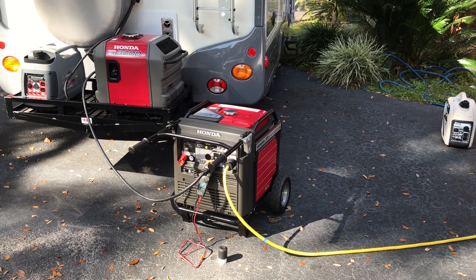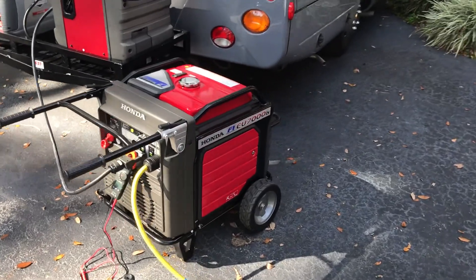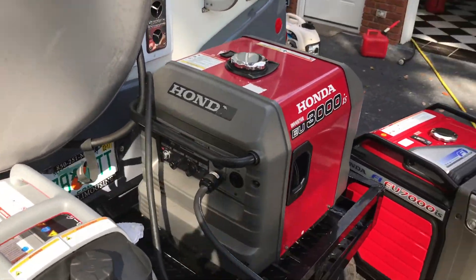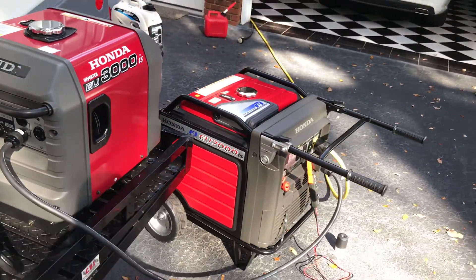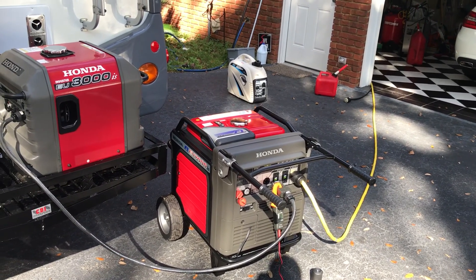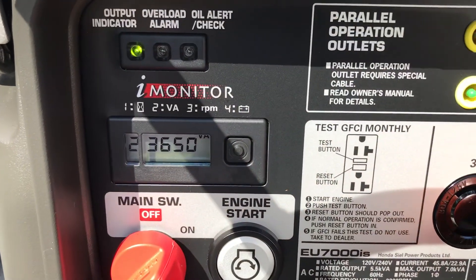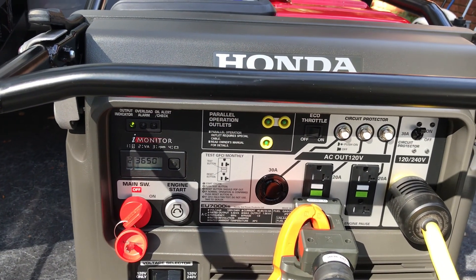Guys, this is a pair of Honda inverters. I have an EU-7000 IS and I have an EU-3000 IS. What we're doing — they're both running. They will not run the 4-ton unit in Eco mode, but you have to leave it in full tilt. The 4-ton unit is using about 3700 watts.